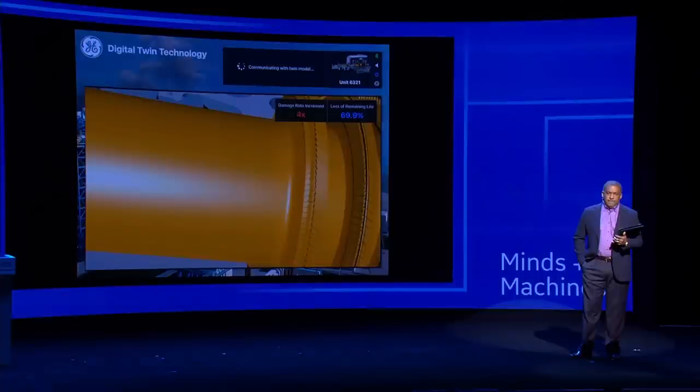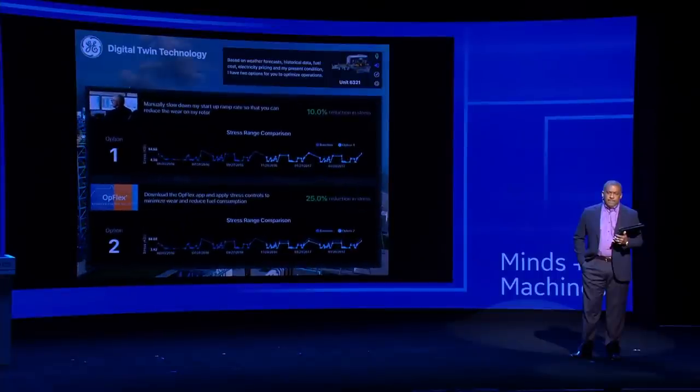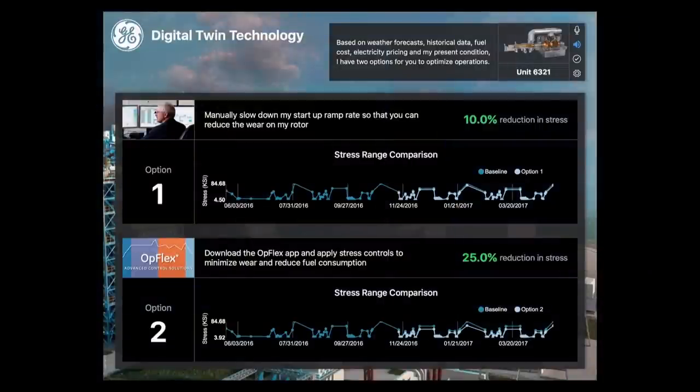Twin, give me options for mitigating that rotor damage. Based on weather forecasts, historical data, fuel cost, electricity pricing, and my present condition, I have two options to optimize operations. Option one is to manually slow down my startup ramp rate to reduce the wear on my rotor. Option two is to download the OpFlex app and apply stress controls to minimize wear and reduce fuel consumption.